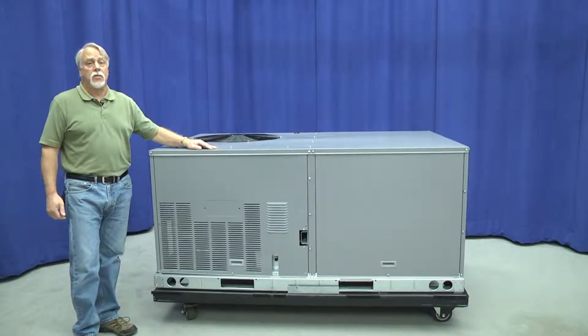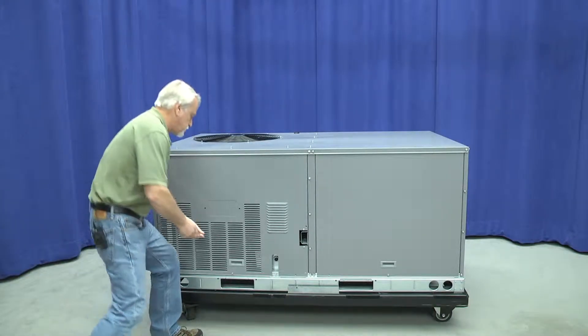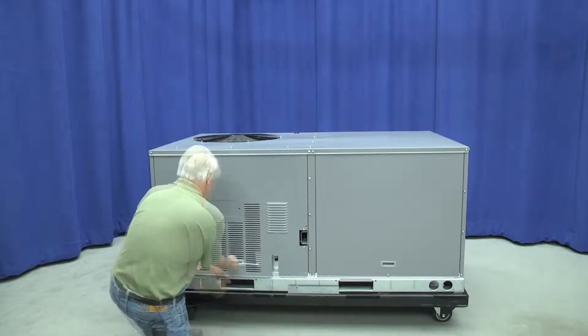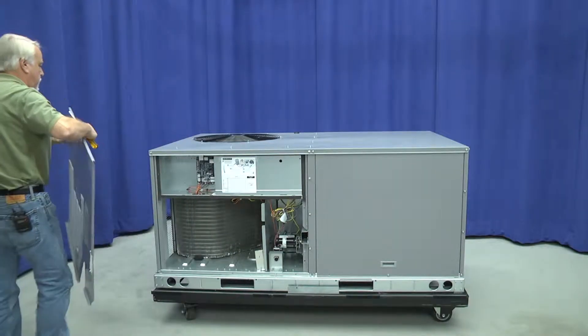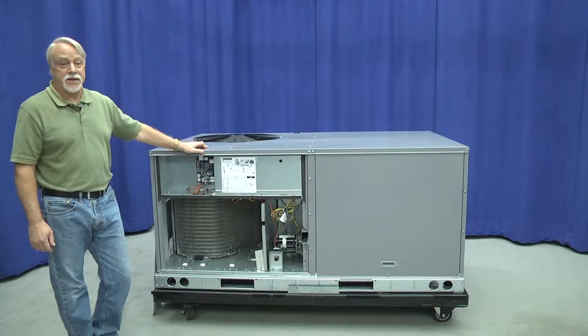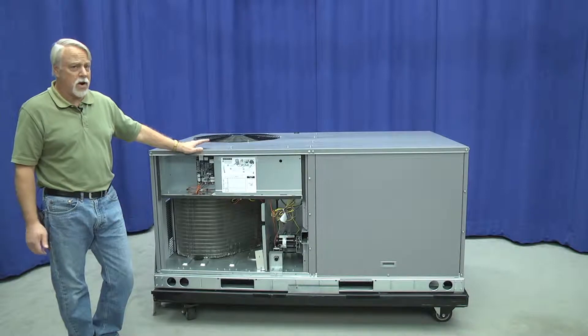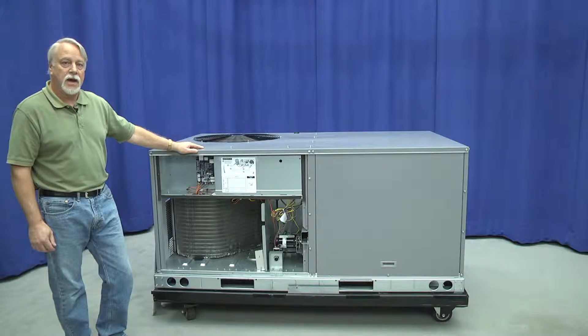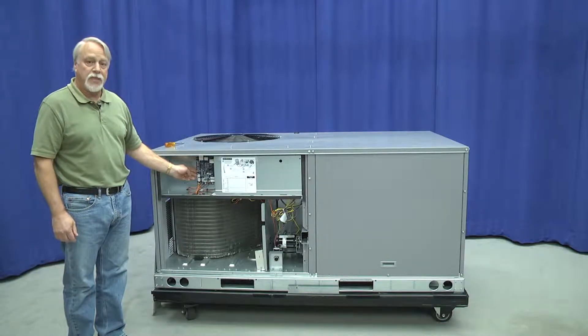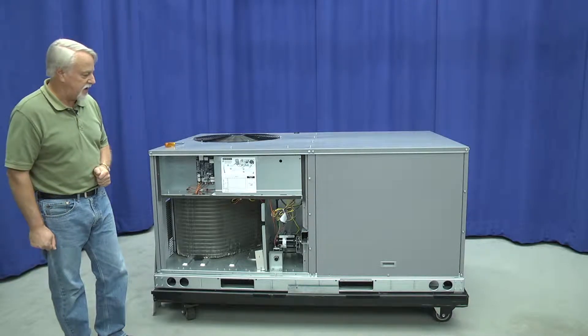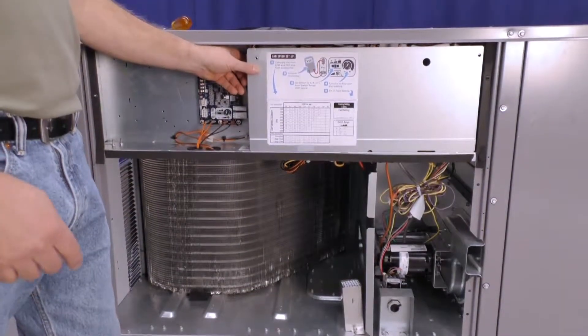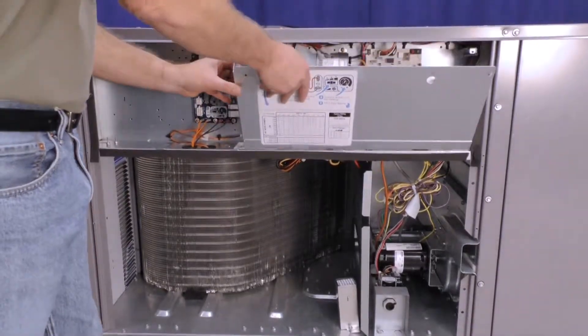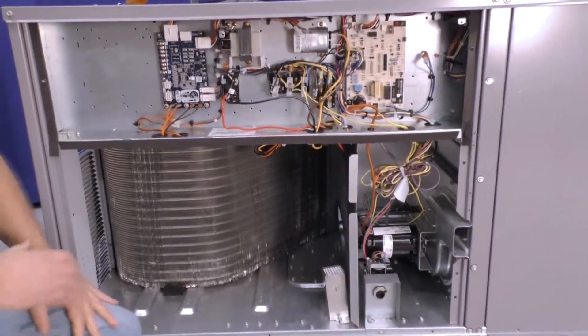We turn the unit around, now we're going to remove the outer panels and see what's different. With the control box access panel removed, we can see what looks remarkably the same with this small rooftop unit. The changes that we're going to talk about are specifically with how I adjust the fan and the changes to the control terminal board which is different with this type of indoor fan assembly. Additionally, notice that there is a sticker that guides us through setting up the air flow levels for the indoor fan. Removing that panel exposes the balance of the control box components.